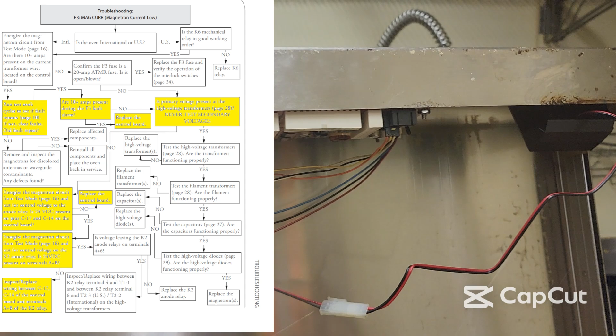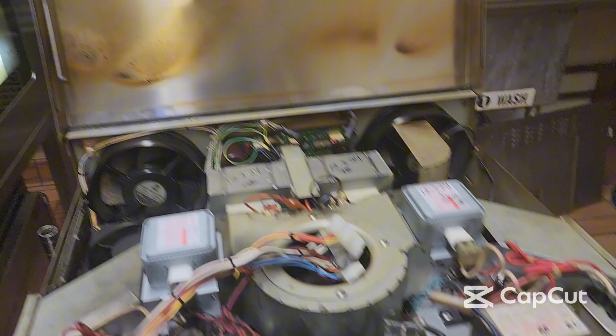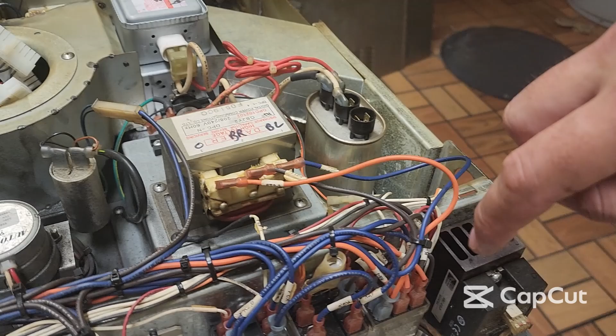Those things you can look for in your test are actually on these back wires. You can be looking for your 24 volt signal to these. So if you push and activate your mag circuit and nothing is happening, you're not getting any amps and you're not getting volts back here.